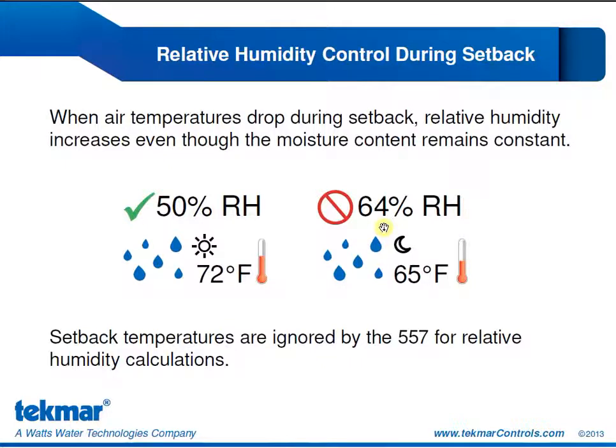So we would enable the dehumidifier and remove some of that water vapor from the air. Well, then what happens the next day as it heats up? That lower water vapor content might be below our relative humidity minimum setting, and then we would be enabling our humidifier. So we'd be encountering some back and forth inefficient operation of the dehumidifier and the humidifier, when what the goal is to keep the moisture content in the room stable. We don't want to be adding or removing moisture as a reaction to the change in air temperature in the unoccupied state. So what the 557 does is it ignores the temperature of the unoccupied state, so it ignores that setback temperature, and instead calculates relative humidity based on the occupied set point temperature.